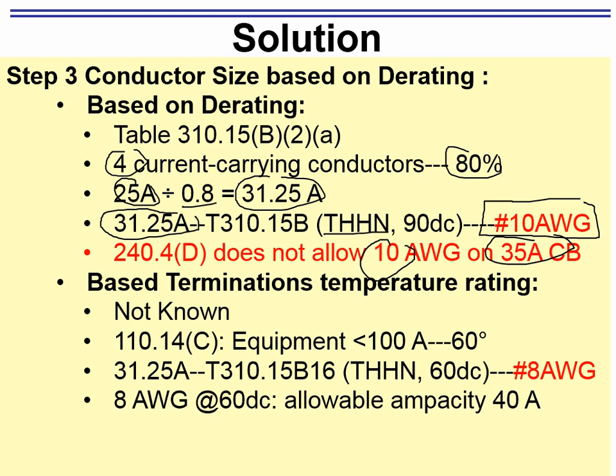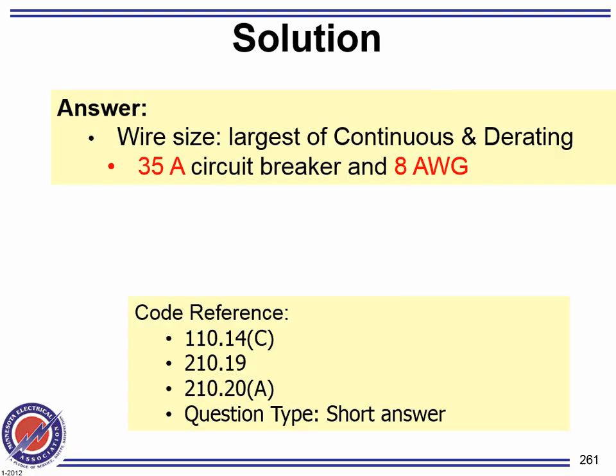So based on temperature, you can go to 60 degree, and for normal operating condition this would be number 8, and number 8 can allow up to 40 amps. So in a case like this, guys, your conductor will be number 8. Why? Because it's the largest, between derating and continuous.